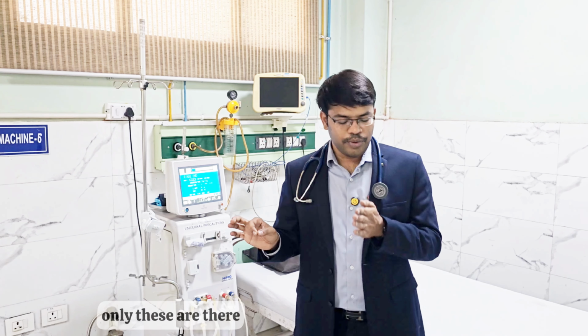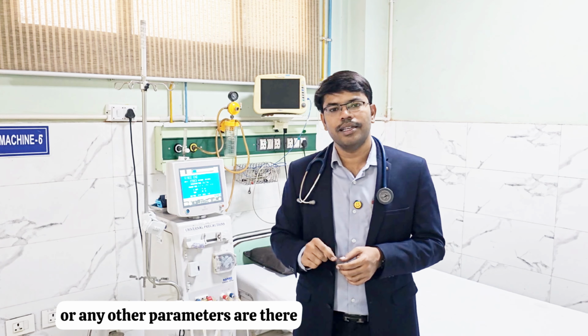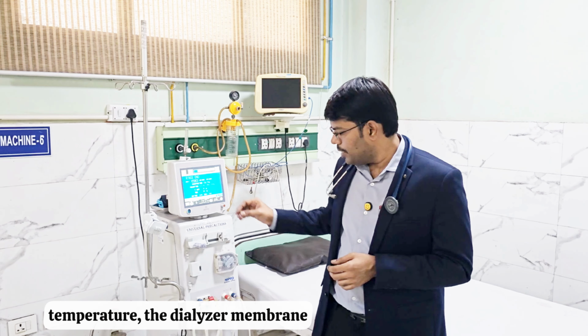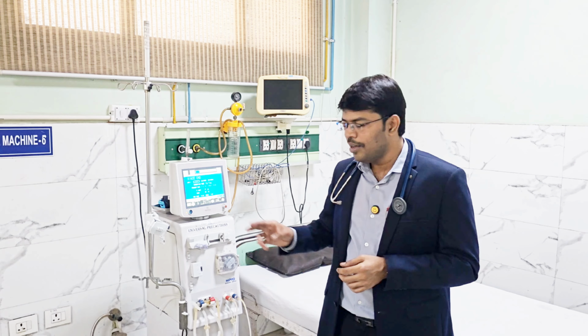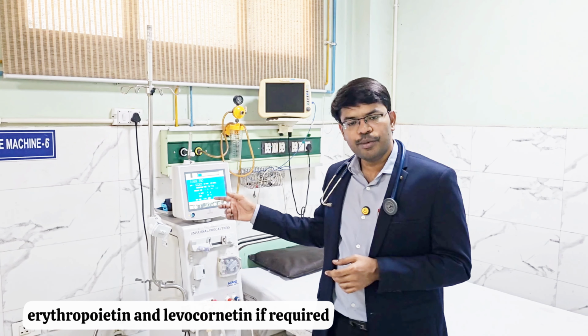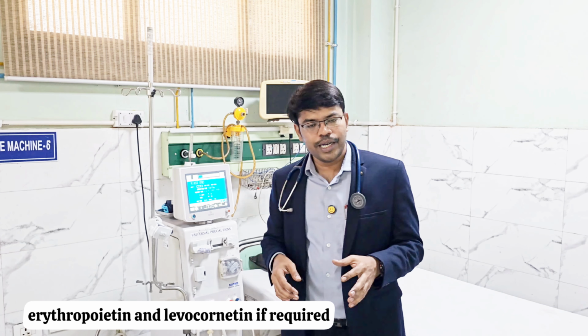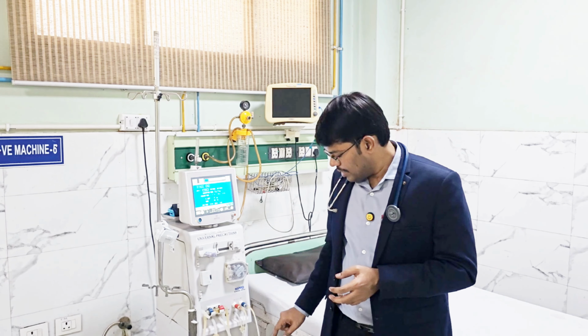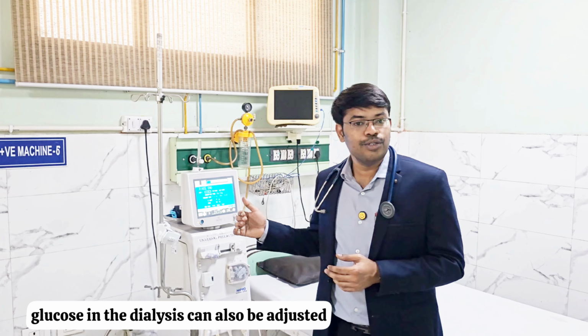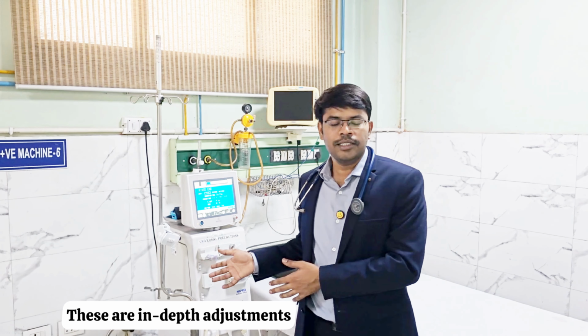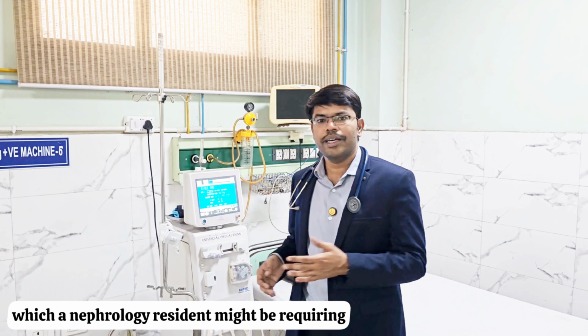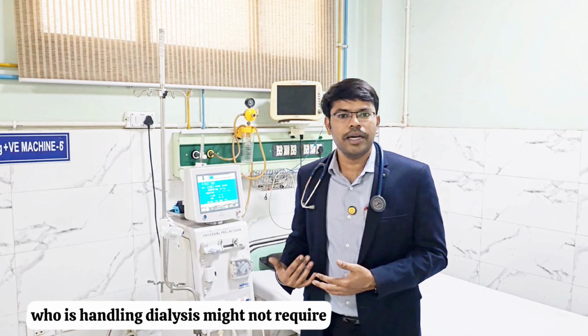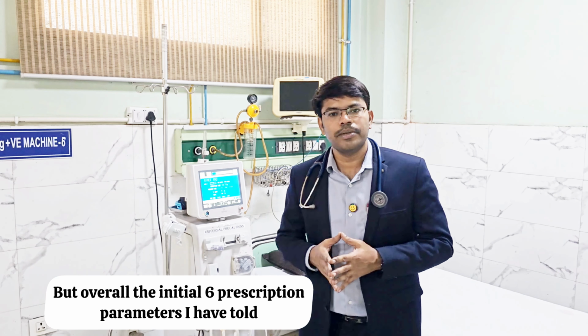Are there any other parameters apart from these? Apart from this, temperature, the dialyzer membrane, whether to reuse it or not, erythropoietin and levocarnitine if required, any antibiotic to be given after dialysis. These are extra information you can add if required. Calcium and glucose in the dialysate can also be adjusted. These are in-depth adjustments which a nephrology resident might require. The general physician who is handling dialysis might not require them. But overall, the initial 6 prescription parameters I have told are required.